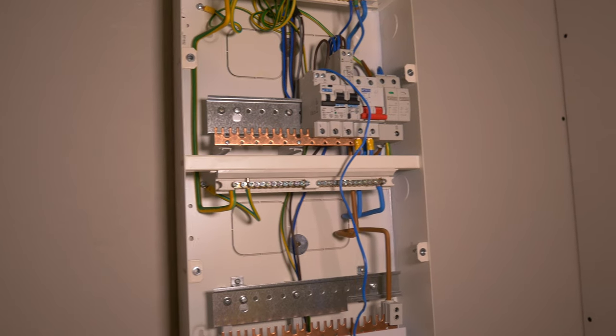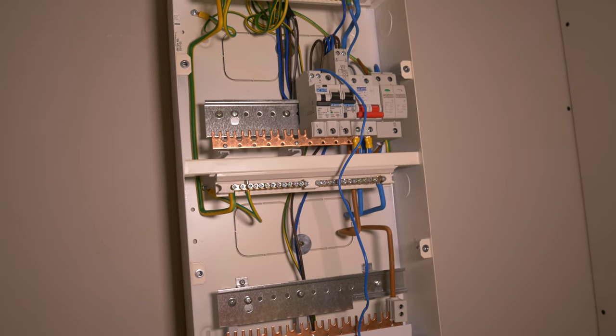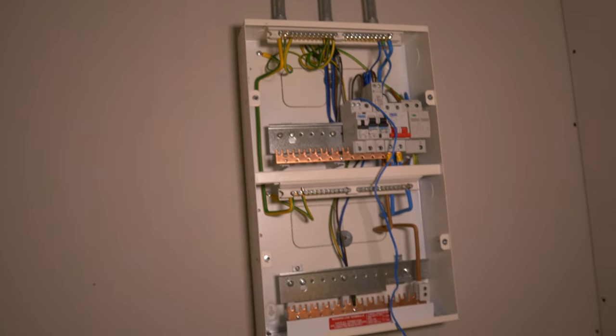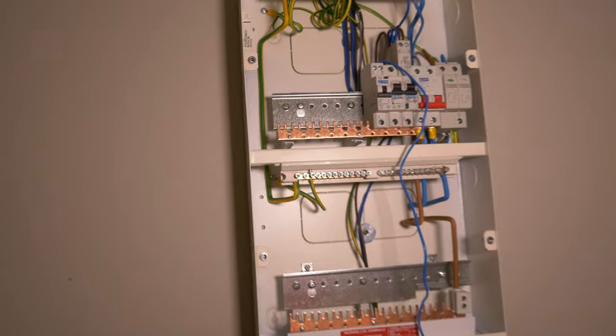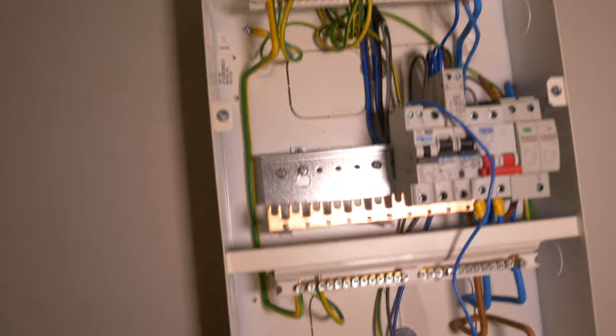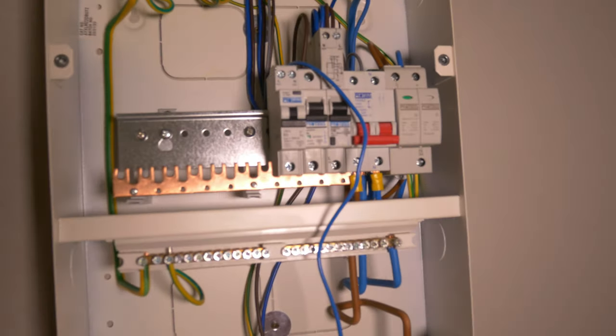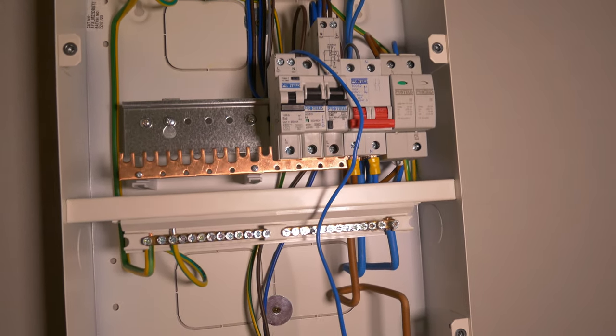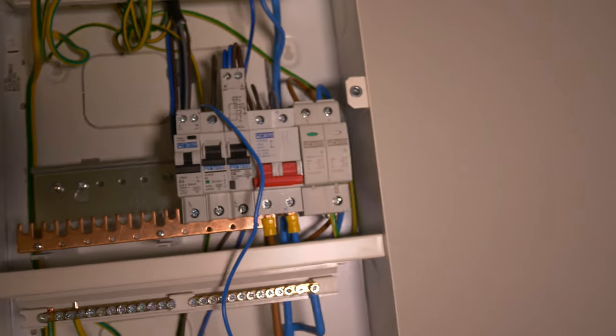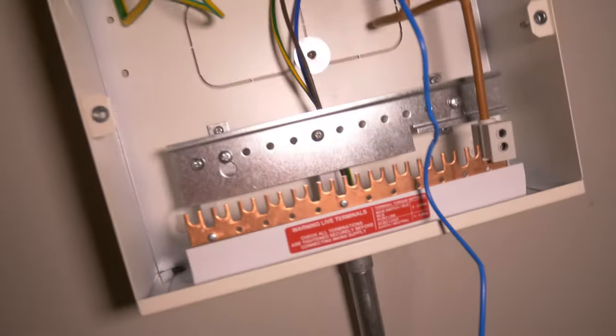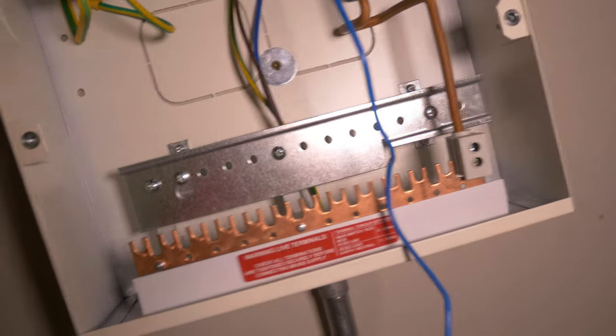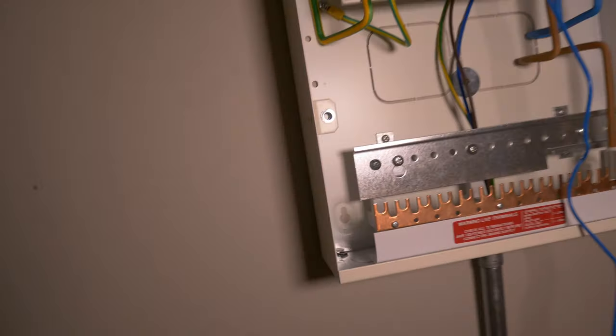So I just wanted to show some of the different overcurrent protective devices on this Proteus board. So this is the twin stacked version, 22 way. You can see the way it's set up here. Straight out the box, this is how it came, aside from the three final circuits you'll see that are in there. So we've got the main switch, and again, the SPD is all pre-wired in the board. This one is a type 2 SPD. And you see down here, it loops across to this bottom bus bar via a connection block, and we're on to another 12 ways down on the bottom half of this board.